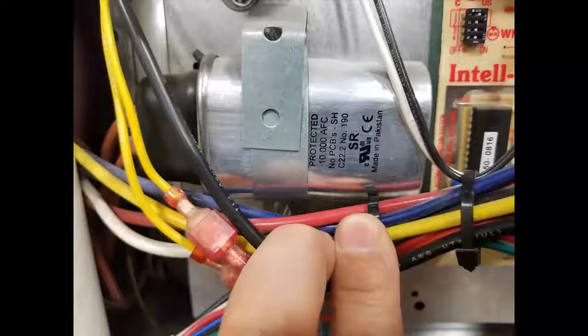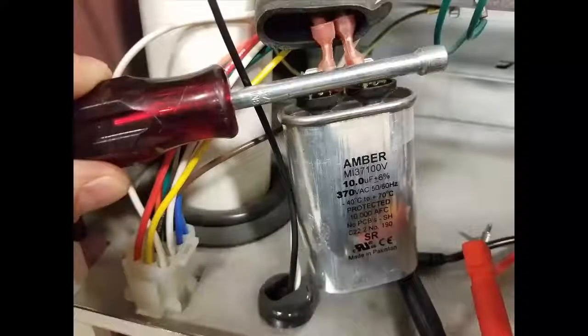So here we have a picture of the start capacitor. We're going to go ahead and pull it out. You need to be very careful with these as they're a device that stores energy. So the power can be off, and if you pull a capacitor and touch the two terminals, you can still get a shock, a very powerful shock. So whenever I pull them, I discharge them. You can do that with a screwdriver or a nut driver, as you see here in this picture. I just place something metal across both the terminals to discharge it.